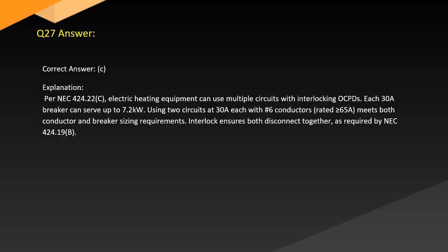Answer. Correct answer. C. Explanation. Per NEC 424.22(C), electric heating equipment can use multiple circuits with interlocking OCPDs. Each 30 amp breaker can serve up to 7.2 kW using two circuits at 30 amps each, with number 6 conductors rated at 65 amps, which meets both conductor and breaker sizing requirements. The interlock ensures both disconnect together as required by NEC 424.19(B).